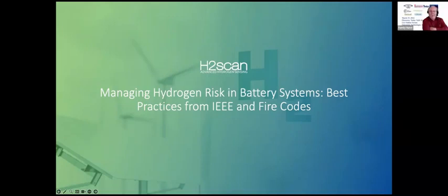Right. We deliver a course on battery energy storage systems and testing and maintenance of batteries, as you know, even for UPS batteries. But one of the questions there is that the focus has always been on the testing of the batteries, their battery integrity, battery performance, but we haven't focused so much on ventilation and containment. Right. So IEEE 1188 is your standard for valve regulated, and 450 is for flooded battery. IEEE 1578 for spill containment, which I actually chair that document. And then of course 1635 for ventilation.